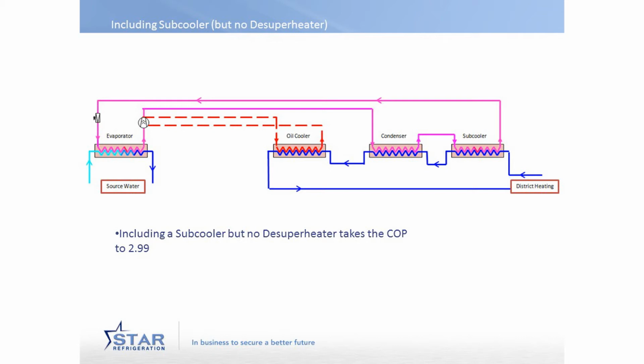Going back to Drammen again, it was a very large system. We actually had 3 heat pumps, and they were all working together to try and get the best possible outcome. To put in context the performance at Drammen, we're getting 3 units of heat for 1 unit of electricity. That's roughly the same that you would get from a domestic heat pump, only heating to 45.